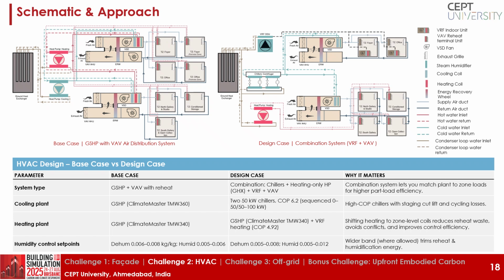For the design case, we revised the system, retaining the ground heat exchanger based on load analysis and performance issues observed in the base case. Cooling was supplied by two water-cooled chillers of 6.2 COP connected in series, which helped minimize cycling losses and improved overall efficiency. For the perimeter zones, a VRF system was introduced specifically for heating since the heat pump alone was unable to consistently maintain comfort conditions. By shifting heating to zone level coils, we achieved finer control and reduced energy for reheating. Finally, we also adjusted humidity control set points by allowing a slightly wider band where possible. We trimmed unnecessary reheat and humidification energy.